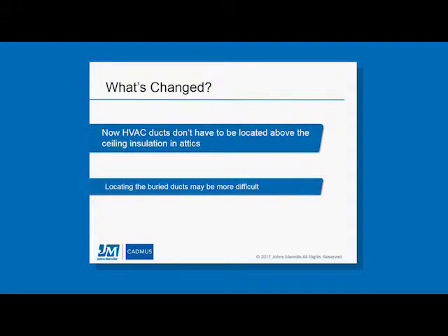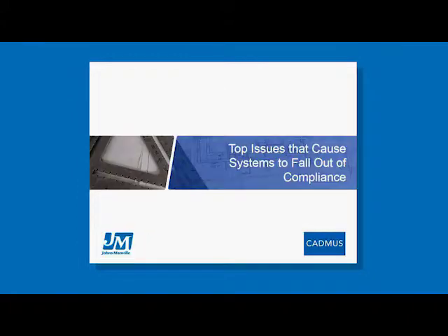So the implications here are that now the HVAC ducts don't have to be located above the ceiling insulation. They can retain a little bit of benefit from the ceiling insulation or the attic insulation. The one caveat is now it might be a little bit more difficult to locate those buried ducts in that attic space if somebody has to service some of the utilities there. Okay, I'll turn it back to Eric now regarding issues that can cause systems to fall out of compliance.